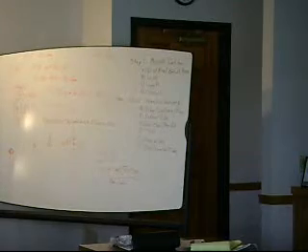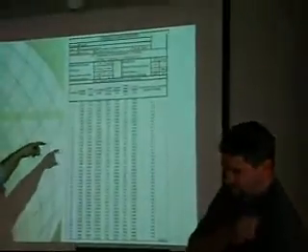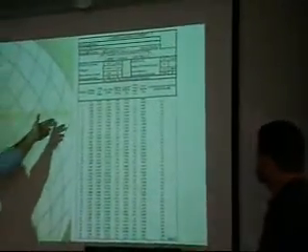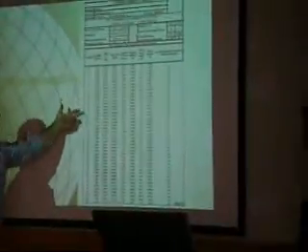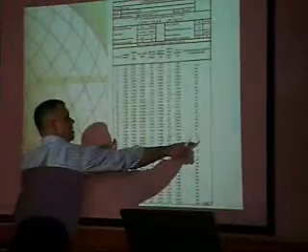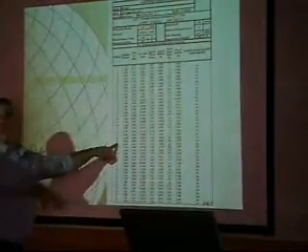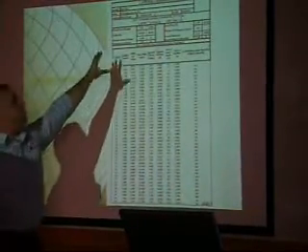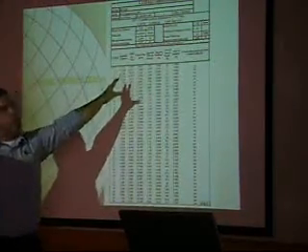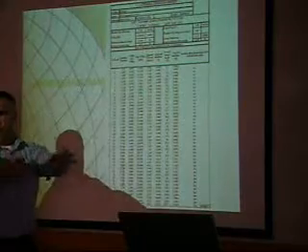The other thing I wanted to show you, I know you can't read it, see this column here? You probably can see the yeses and the nos in this column. This is kind of a slick little calculator this gentleman's got, because what it does is orifice 1, orifice 2, on down the road, and the yeses and nos tell him where the flow differential is greater than 10% with all the specs he chose. 1.5-inch pipe, 3/16-inch orifice spacing, all the rest that he programmed into there.